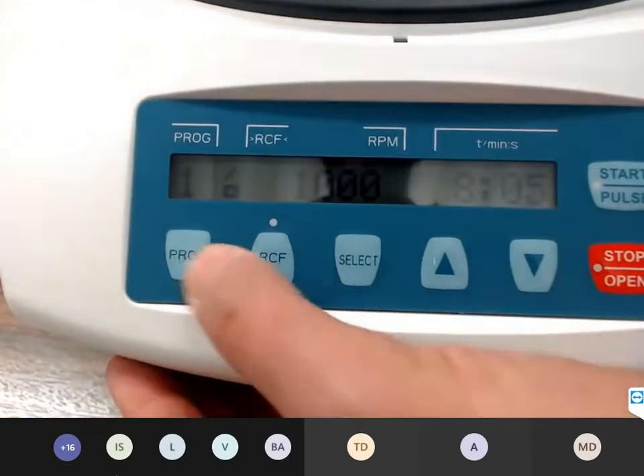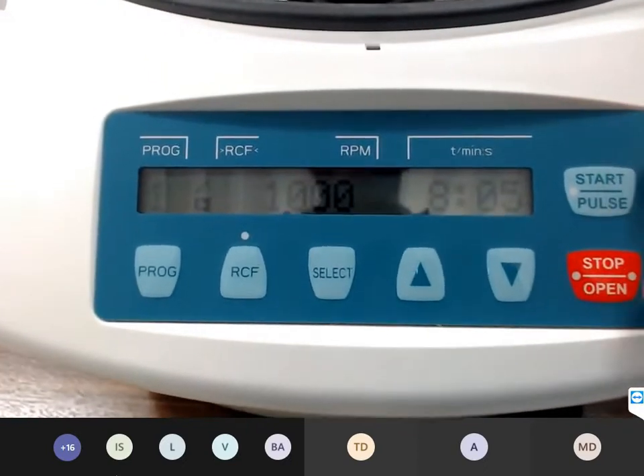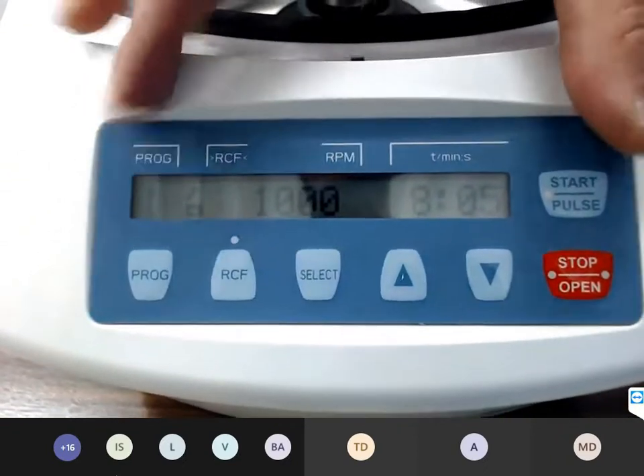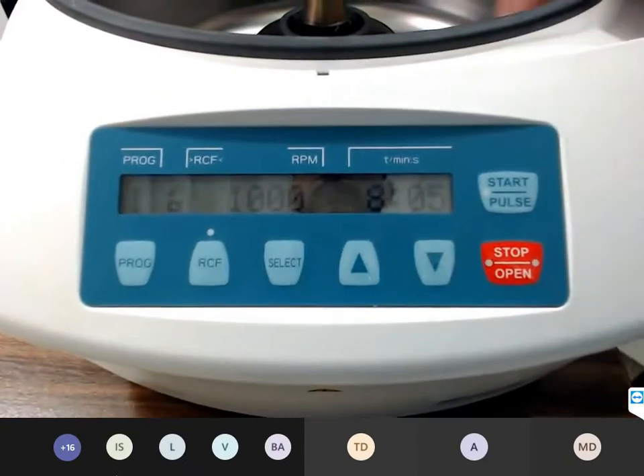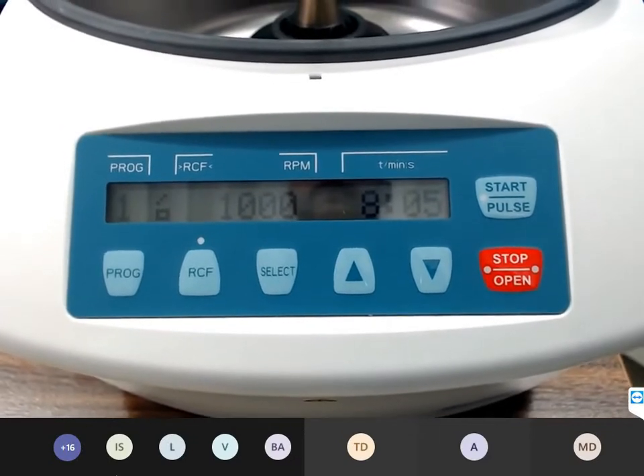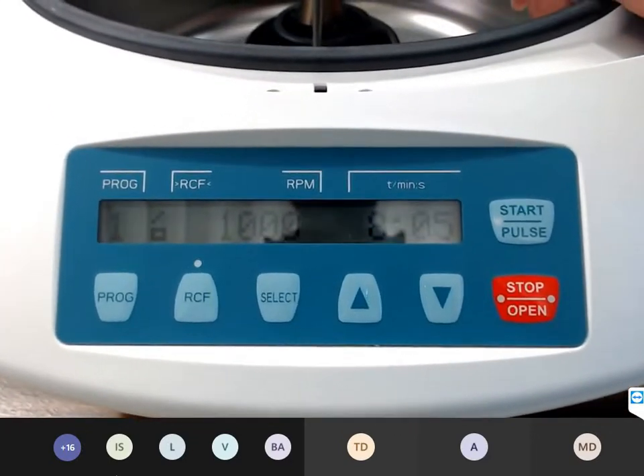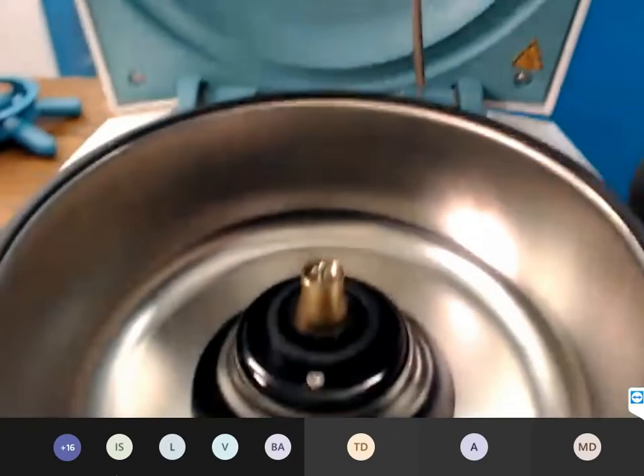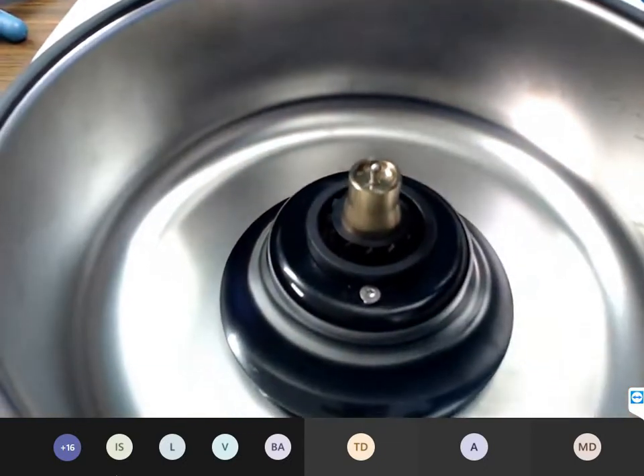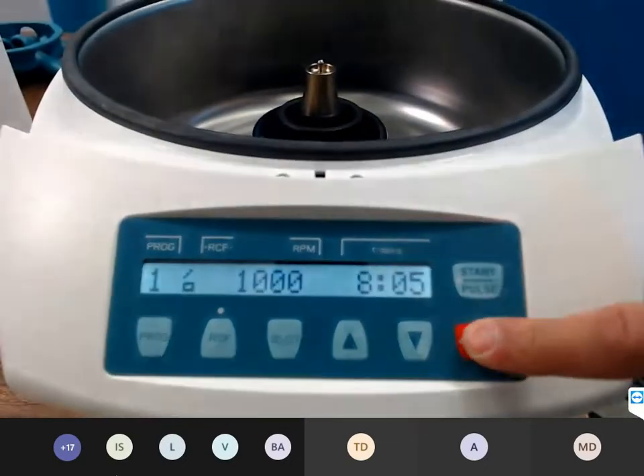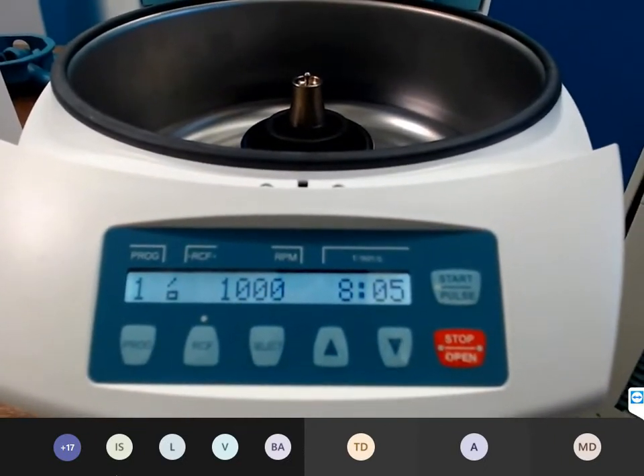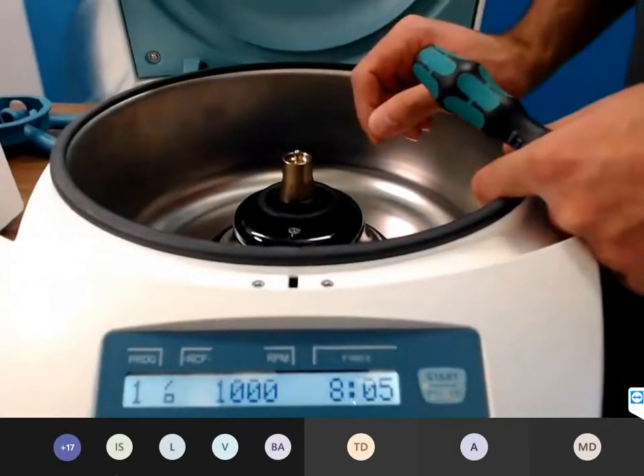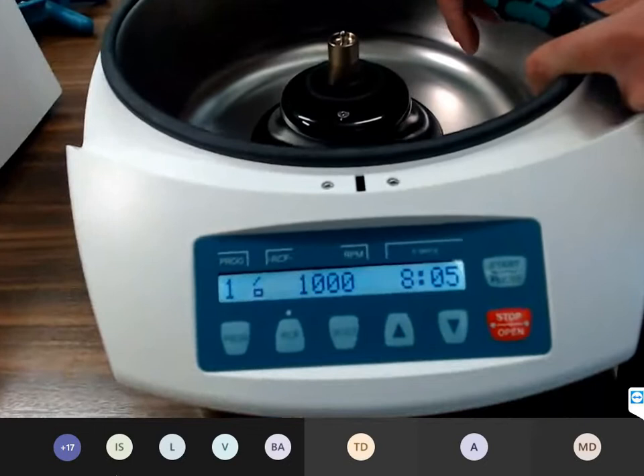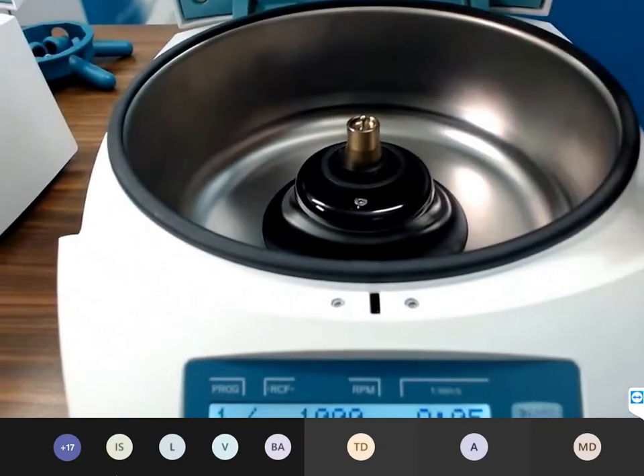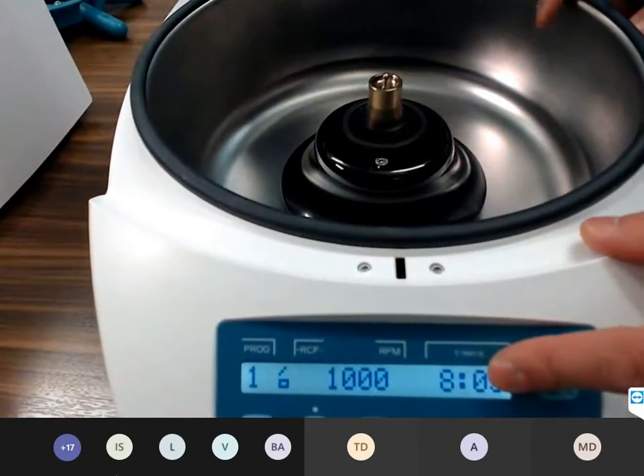In case of error or if the keys don't work, you can only check the foil. You don't need to replace the electronic part of the M control board. So remove the motor cover again. We have here also different service menus. The imbalance detection is the same like the EBA, micro, and hematocrit. We have here a Hall sensor detection, the setting, the adjustment of the imbalance detection is the same one.